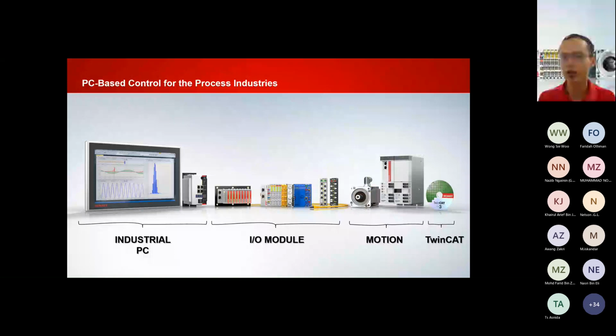If you look at the bottom, the PC-based control uses the remote I/O concept. The I/O terminal is modular with a 12mm width, and you can directly terminate the field termination cable into it. It is highly scalable because the CPU of the PC, with high processing power, can cater up to 65,535 I/O in one control system. The card is easily expanded and scaled up—just connect and expand to the right side, side by side on the remote I/O.